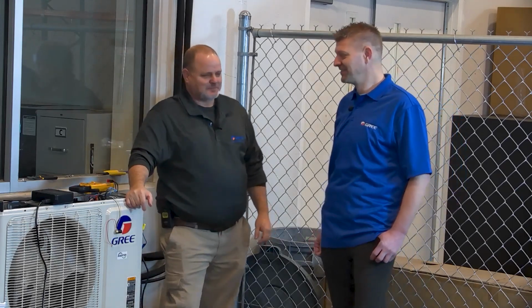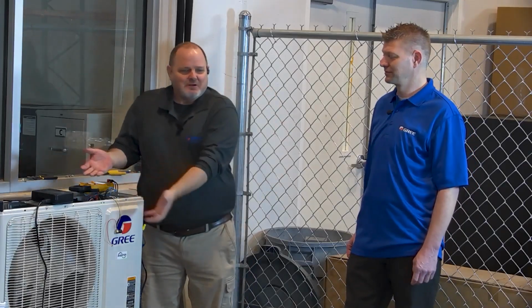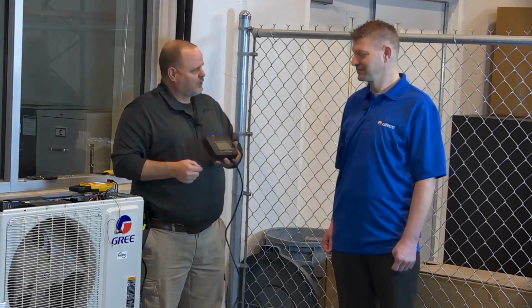Subcooling. Everybody loves to talk about subcooling. And you've had this question how many times: what should the subcooling be on that mini split unit? So I'm going to answer that question. We don't know. Because they're variable speed machines. You can't lock it into a speed. You don't have a TXV. TXVs are great metering devices, nothing against them. Are they as precise as an EEV? No. No way. Never. The thermistors, GREE's already got them on there for you. They give you the eyes and ears into the system. You just need the service tool that's going to read that for you.